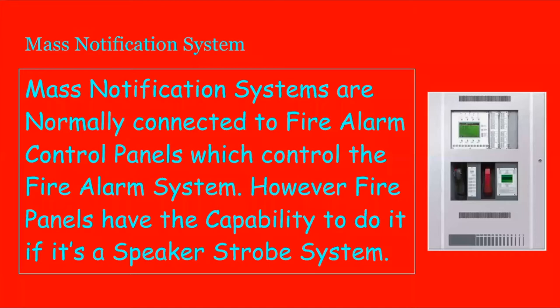Mass notification systems are normally connected to fire alarm control panels, which control the fire alarm system. However, fire alarm panels have the capability to do it if it's a speaker strobe system. So if you have a system like mine, which is a horn strobe system, you will not be able to do that unless you're doing it through an external intercom, which is not run through the fire system. But mass notification systems don't only come in fire systems — they also are outside of fire systems, so they can be related with tornado sirens and other sirens like that.